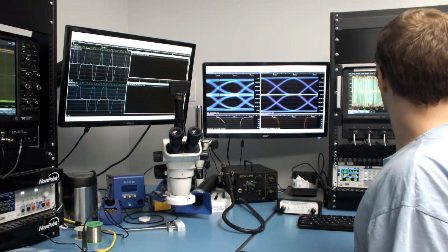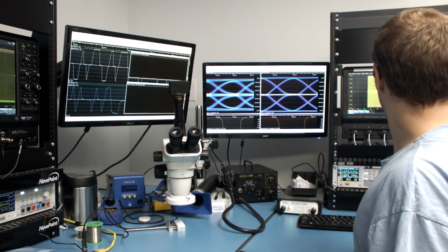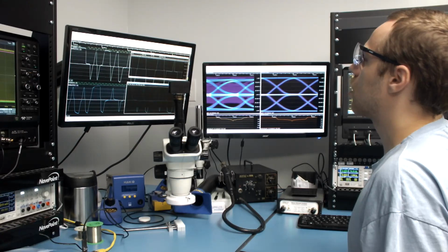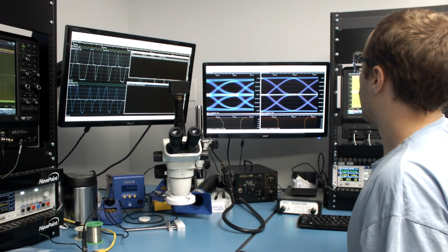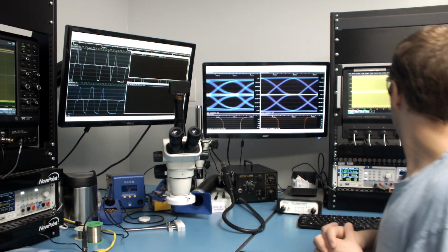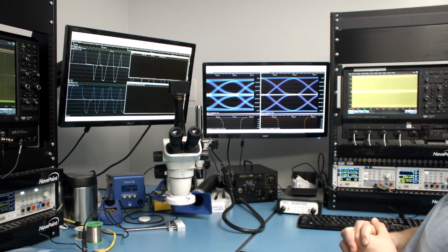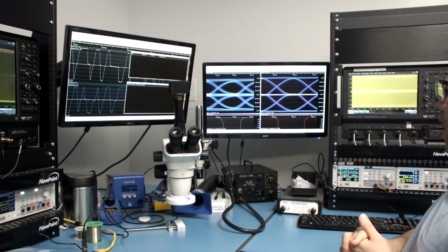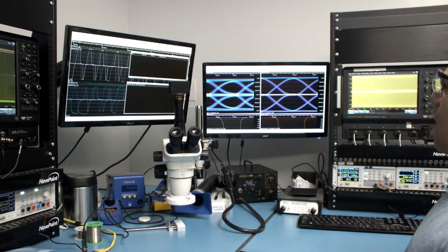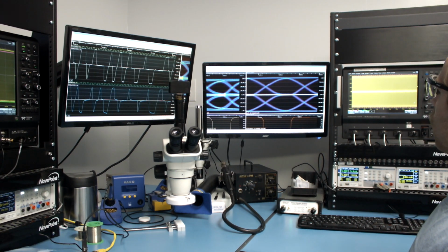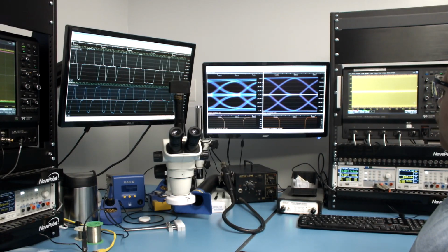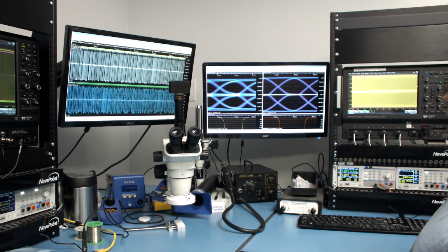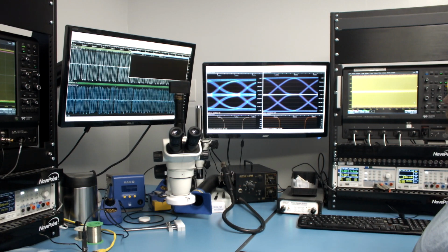So now let's zoom out a little bit and pull up some more points. Okay, let's just clear our waveforms now that we've adjusted our sampling rate. And so now we're at 5 million points at 10 gigasamples per second. So now we're down to about 2 waveforms per second, but you can see it's still working just fine, and the user interface is very responsive. A little bit of lag, but not that bad. We can scroll in and out here, and again, very fast, no significant slowdowns.